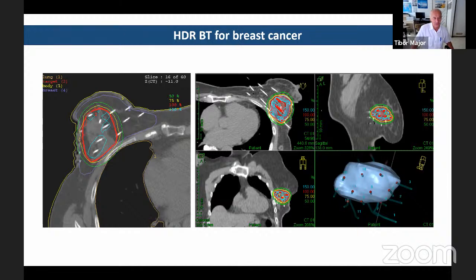With a special software using optimization algorithm, we can calculate the source positions and the source irradiation times. And here you can see the final dose distribution. Here there are two red lines. The thick one is the target volume, which has to be irradiated. And the thinner one is the reference isodose line. This is the 100%. And you can see the very nice coincidence.